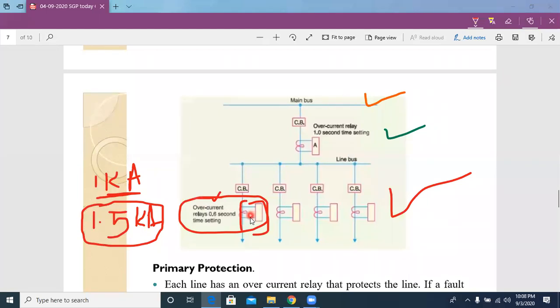One more important thing: the relay is activated immediately when there is a difference between the real value and the preset value, but to operate it takes 0.6 seconds. That is the time, and based on time we decide the nature of the relay. After 0.6 seconds only can it send a signal to the circuit breaker.